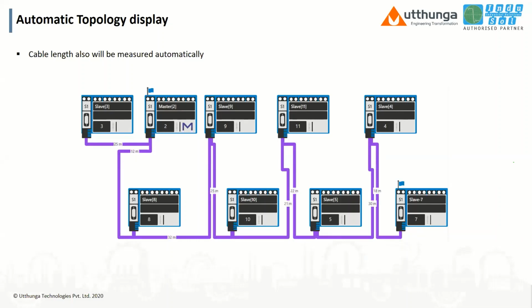And the key point for the signal quality tester PBQ1 is that we can have the automatic topology with correct cable length. Why is topology important in a Profibus network? I have visited a lot of plants, but no plant has a proper topology. They just have an electrical drawing. What will happen in future when the network goes down, when the Profibus communication goes down? Maintenance people don't know where the nodes are located or what the cable length of each node is.